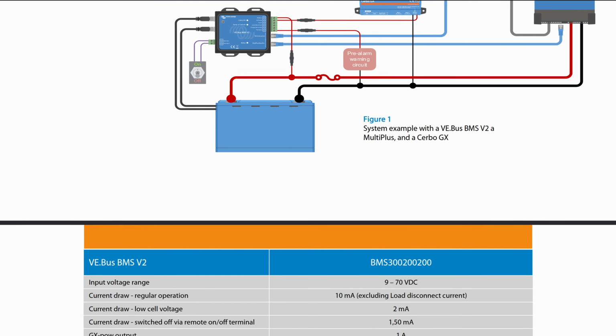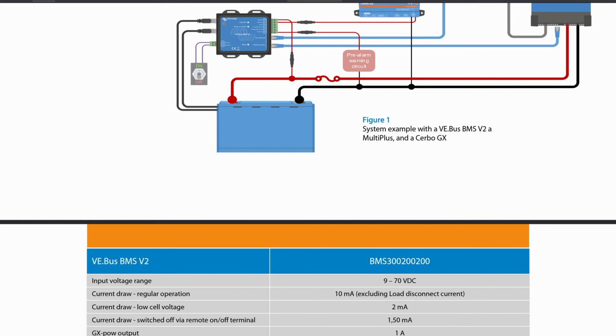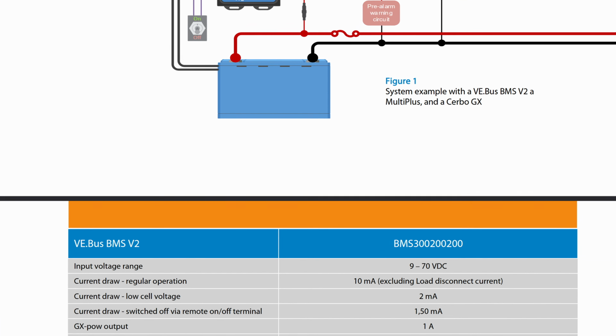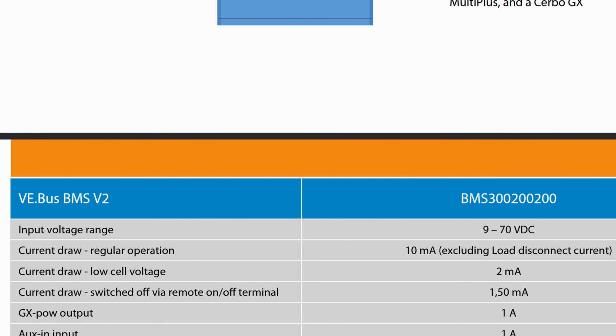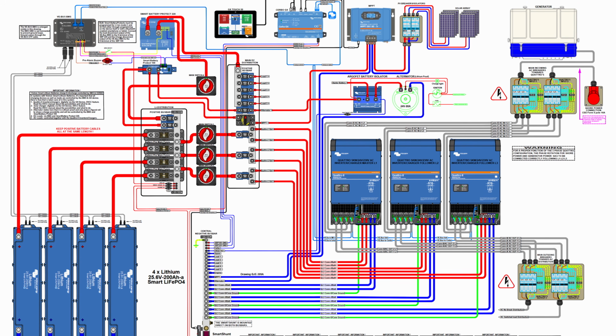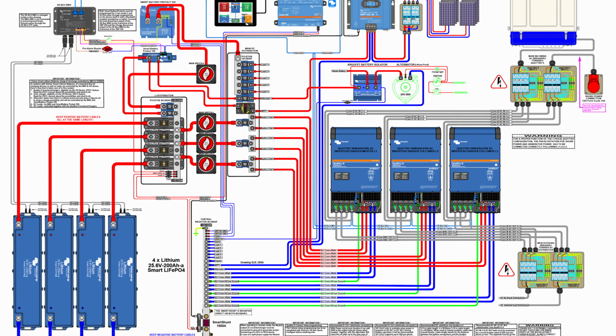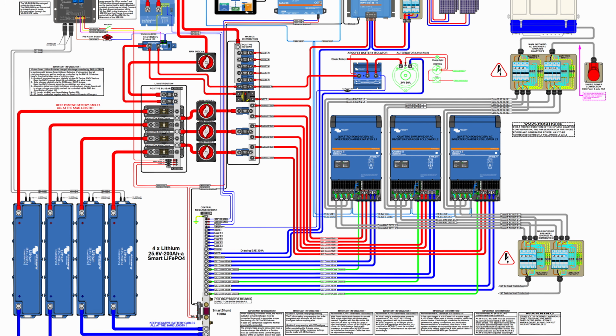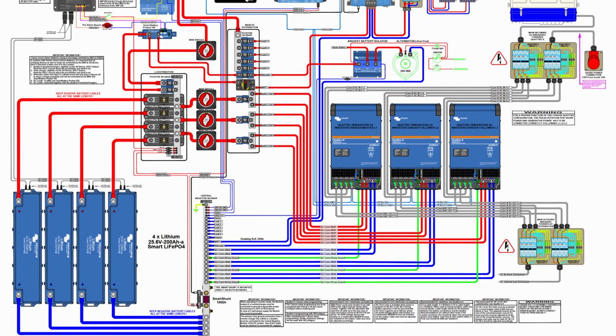Running on 3 to 400 volts DC means we cannot use standard Victron or any other brand drop-in LFP batteries. Theoretically, we could string 15 of them together and you would also have the right voltage, but electrically that does not make it a safe battery. For example, a Victron battery management system does not support a system voltage higher than 70 volts. That means if we exceed that, there is no safety approval and certification, monitoring and charging is going to be a problem, and it's unknown how the system will behave on the whole.